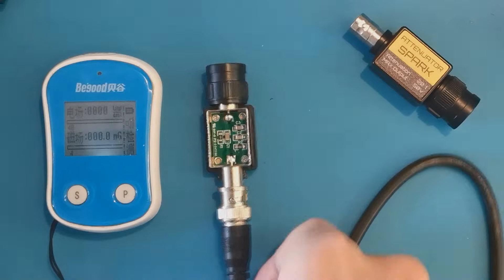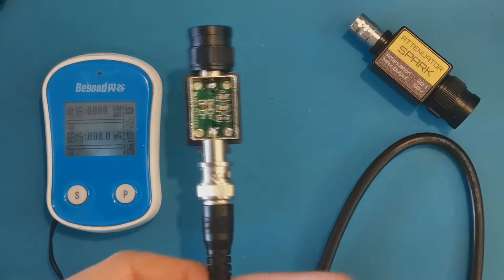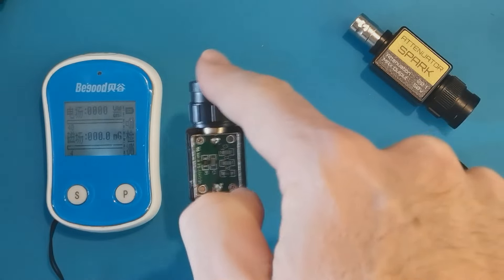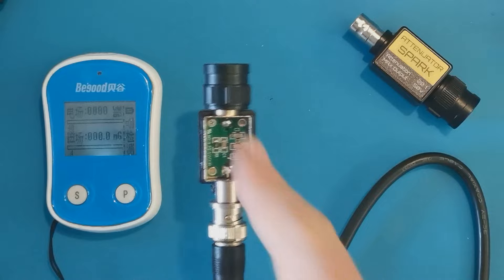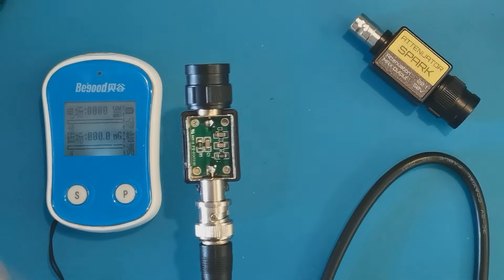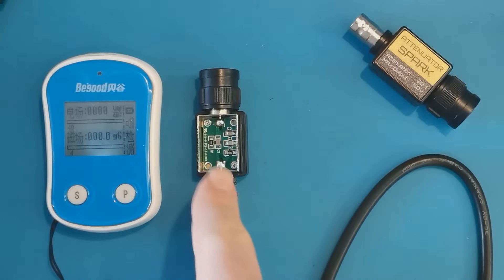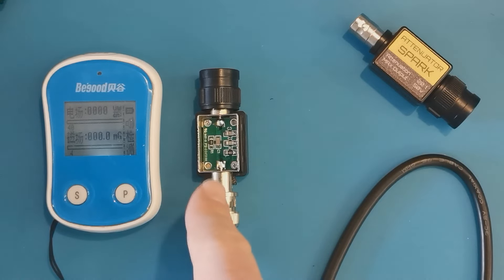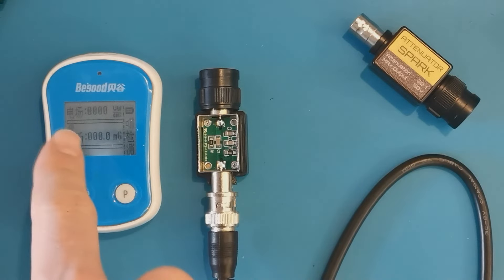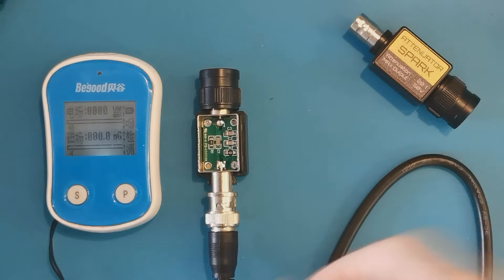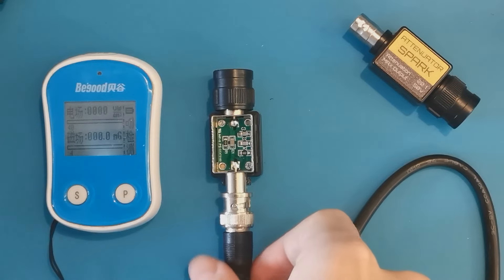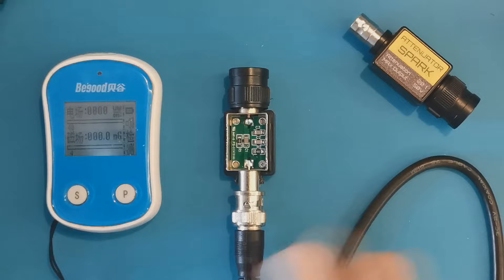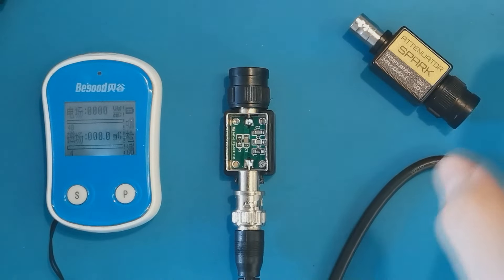The danger of this part is not only in the spark and the device that is behind here, but is also in all the surrounding devices. Because this spark in open air is going to generate an electromagnetic field very very strong, as we saw from the instrument. So actually if you have a computer nearby, devices, laptop, whatever, it is going to probably stop during the test.